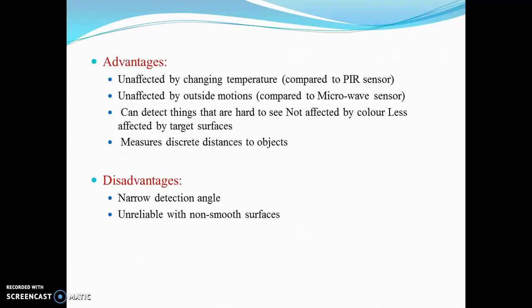The advantage of the ultrasonic sensor compared to the PIR sensor is that it is unaffected by changing temperature, and also unaffected by outside motions, which is compared to the microwave sensor. It also can detect things that are hard to see, is not affected by color, and is less affected by target surfaces. It also measures the discrete distance to an object. But here are some disadvantages of this ultrasonic sensor: a narrow detection angle, and it is also unreliable with non-smooth surfaces.